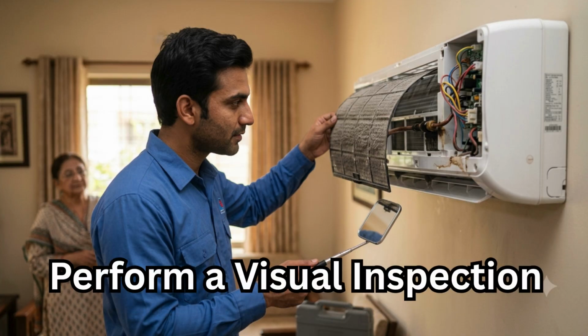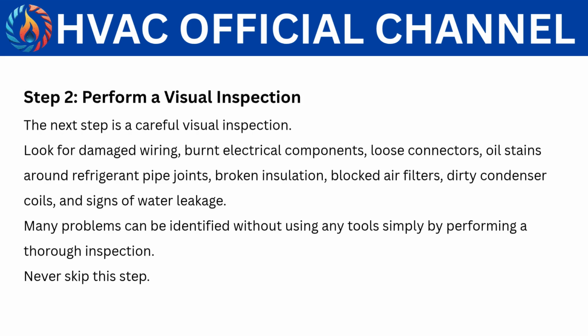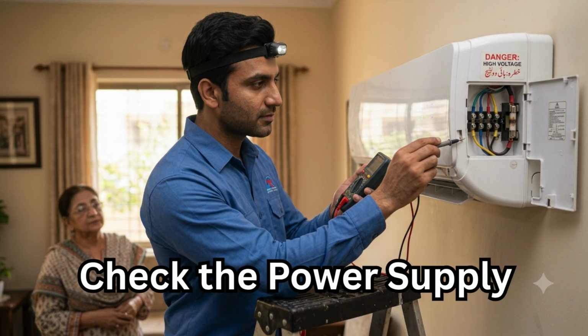Step 2. Perform a visual inspection. The next step is a careful visual inspection. Look for damaged wiring, burnt electrical components, loose connectors, oil stains around refrigerant pipe joints, broken insulation, blocked air filters, dirty condenser coils, and signs of water leakage. Many problems can be identified without using any tools, simply by performing a thorough inspection. Never skip this step.